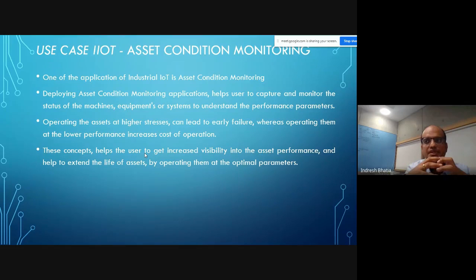If I detect that my system is getting stressed out, that the voltages are always above a given threshold, then I can say for sure that my operating life will be reduced, and I can do something about it. And if the load that this transformer is providing is less than expected, then it's an underutilized asset. I don't need such a high-rated transformer for this application. Although it was initially designed for this, the actual usage is not that much, so I can use that information to see the condition of my asset.